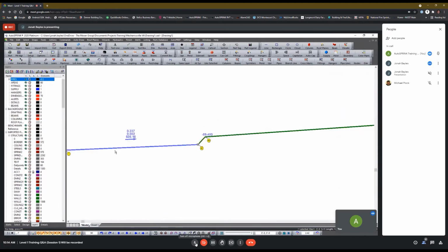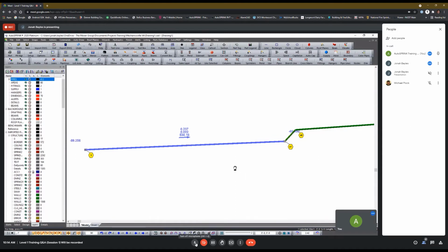Okay, so let's take a look at this pipe you have selected. What these values represent, the right side, that is the pressure that's required at that point. The middle values, the bottom value just above the arrow, that is your system flow demand through that segment of pipe.